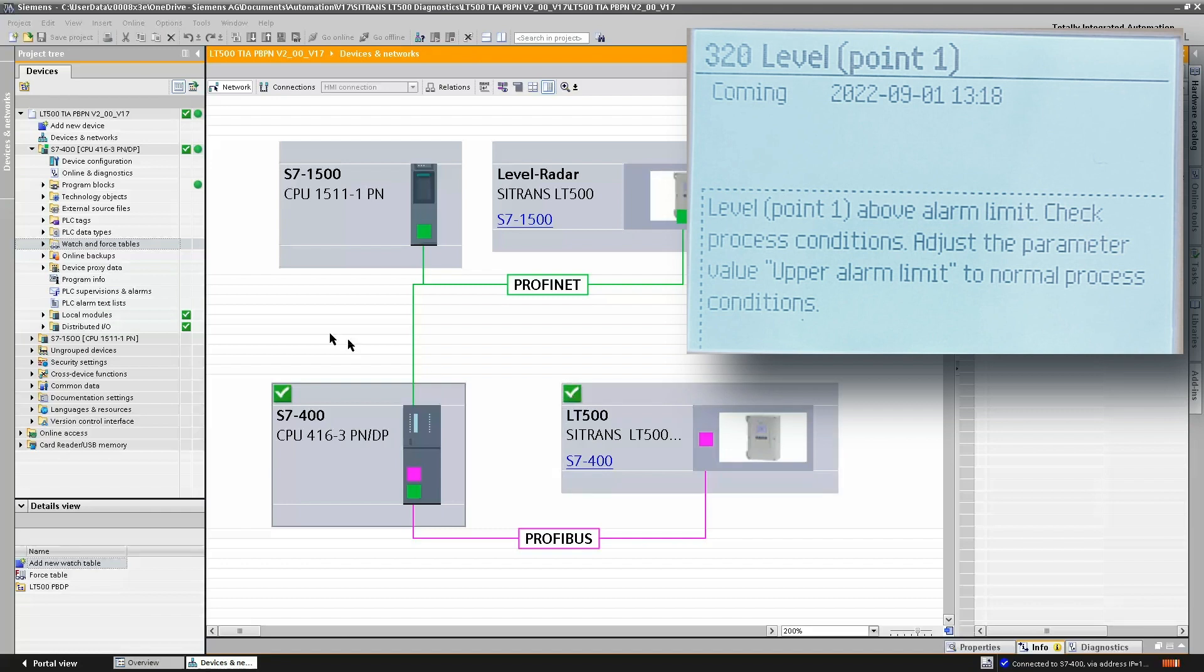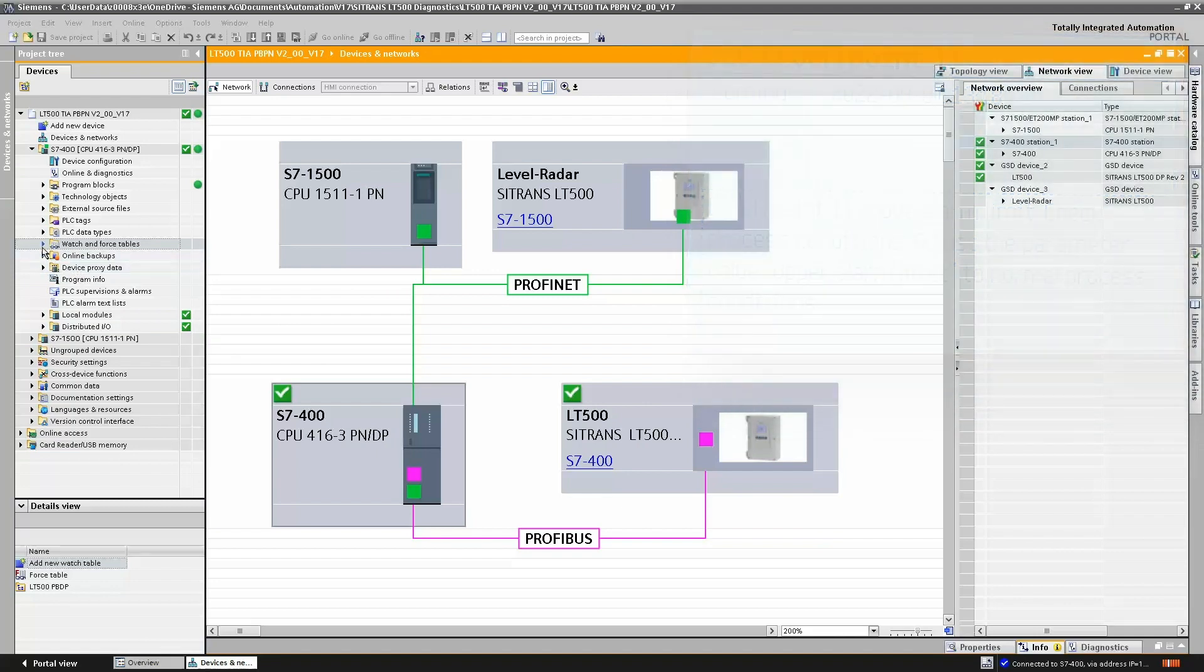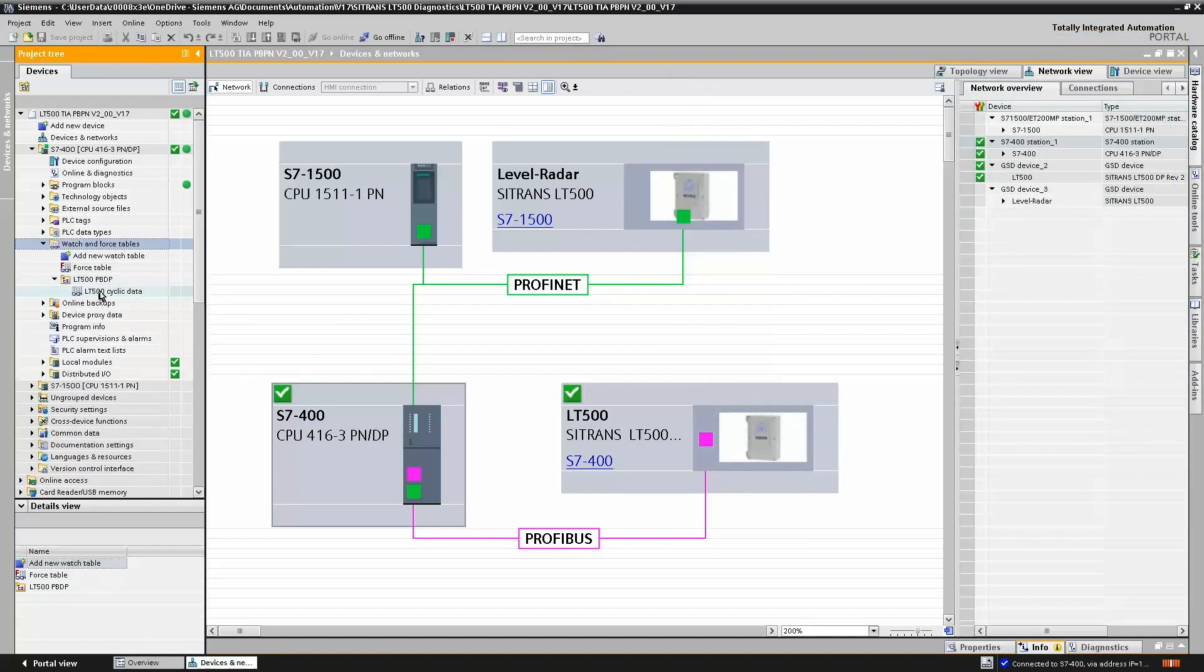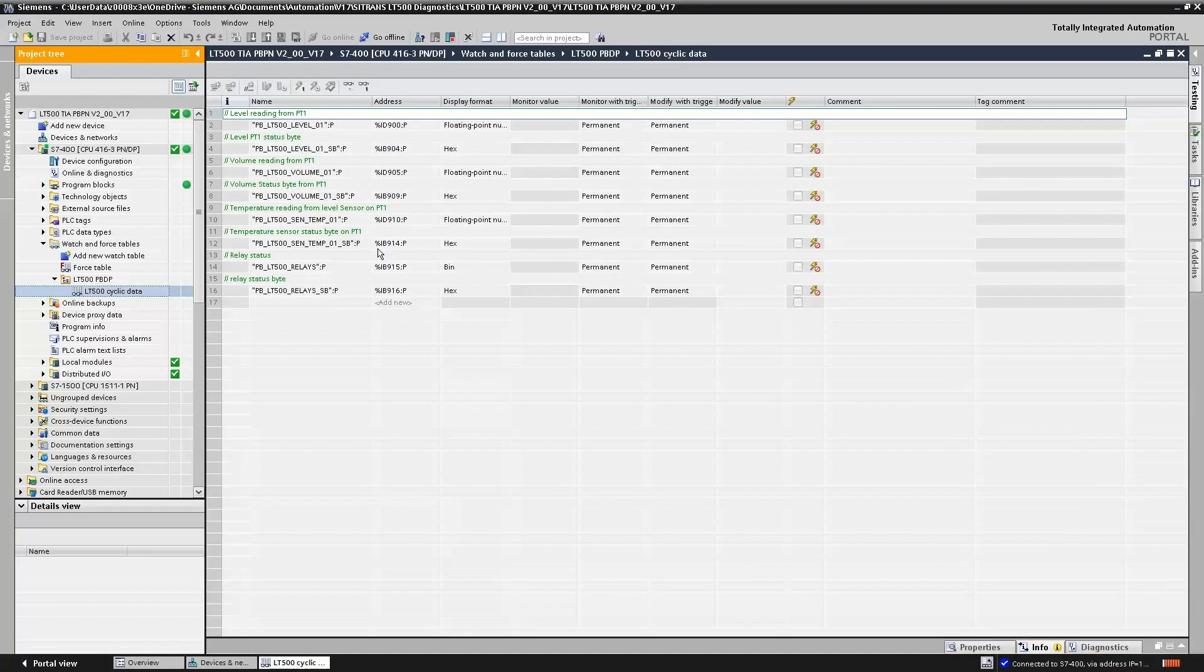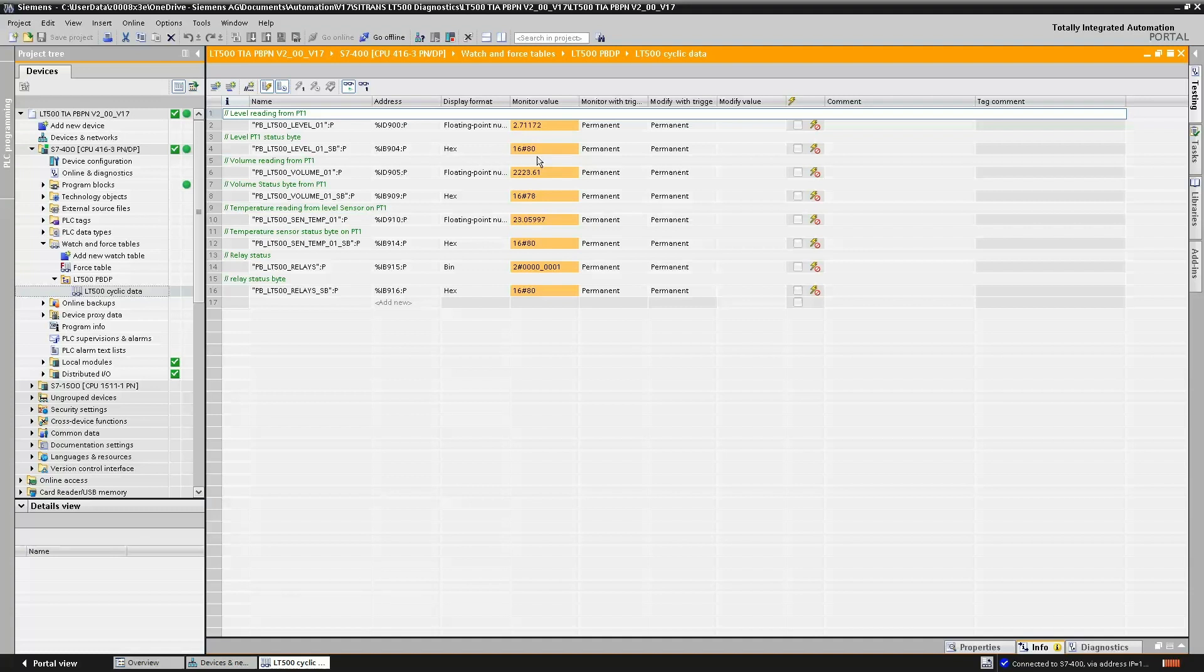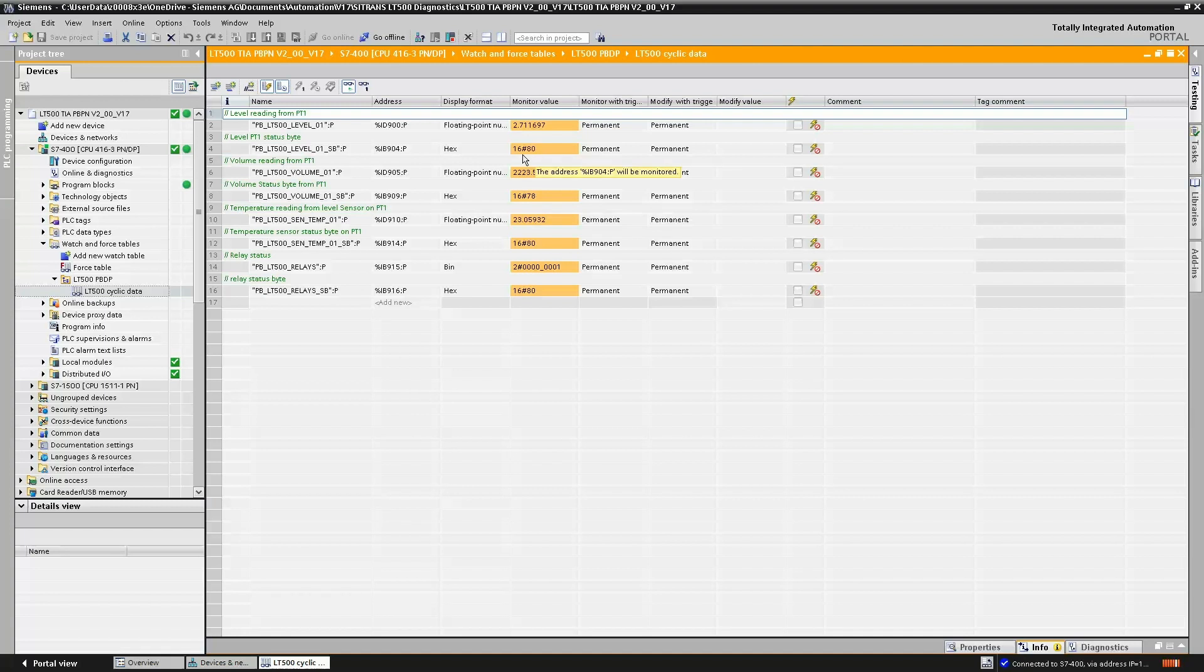If we open our watch table, we can get live data of what's actually going on. If we go online and have a look at our level status, we see that our level status is at 0x80, which means everything is good. If we had an alarm, we would typically expect to see some kind of change in the status point.